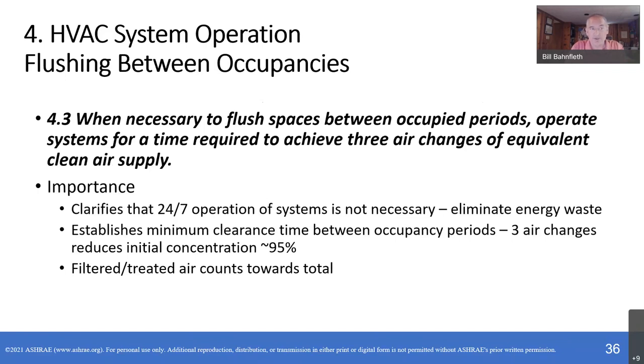The next deals with this issue of flushing. Initially, we were recommending a fairly long flush before and after every working day for an office building. And now the statement is flush spaces between occupied periods when necessary for a time equivalent to achieve 3 air changes of equivalent clean air supply. The importance of this is that it is moving away from the 24/7 operation requirement that we don't think is necessary and is energy wasteful and expensive.